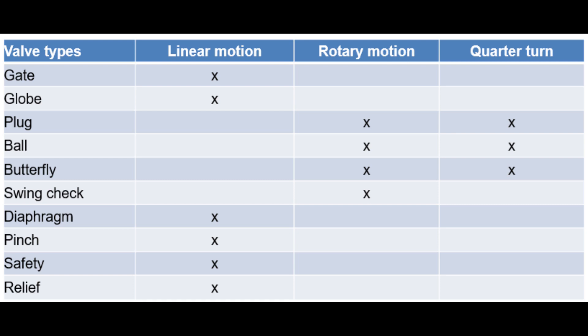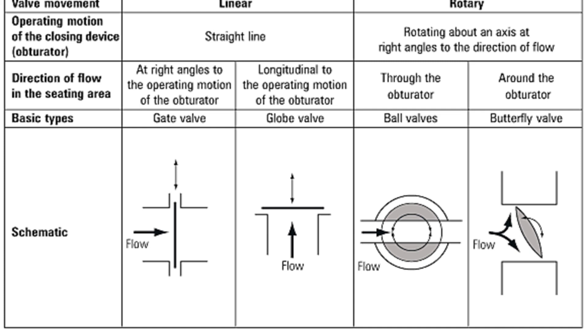Referring to the classification table: gate valves, globe valves, diaphragm, pinch valves, safety valves, and relief valves are classified as linear motion. Plug, ball valve, butterfly valve, and swing-check type valves are classified as rotary motion valves. As shown in the schematic, in linear motion valves flow is directional — either straight or upward — while in rotary valves the fluid travels along an angular path.